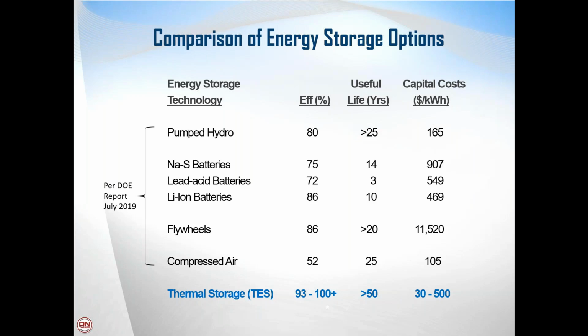And when you compare it to the bottom row, which is chilled water thermal storage, the chilled water thermal storage is more efficient, it's got a longer useful life, and is typically lower in first cost than any of those other types of energy storage systems. So when there's an opportunity for an owner or an engineer to consider energy storage, one of the first ones that should be looked at is thermal storage.